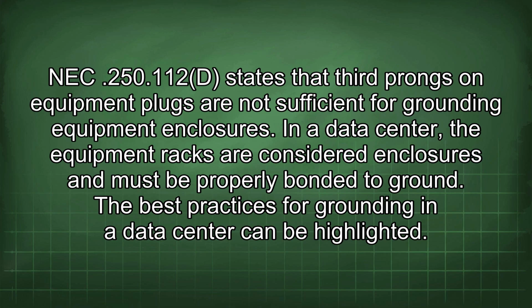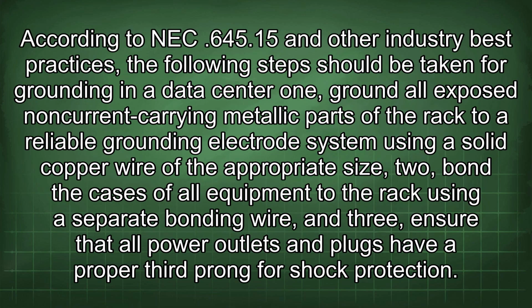The best practices for grounding in a data center can be highlighted. According to NEC 645.15 and other industry best practices, the following steps should be taken for grounding in a data center. 1. Ground all exposed non-current carrying metallic parts of the rack to a reliable grounding electrode system using a solid copper wire of the appropriate size. 2. Bond the cases of all equipment to the rack using a separate bonding wire. And 3. Ensure that all power outlets and plugs have a proper third prong for shock protection.